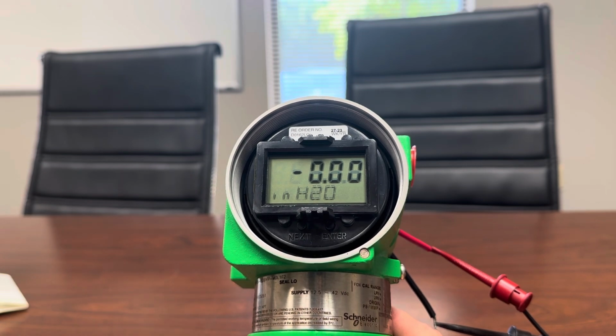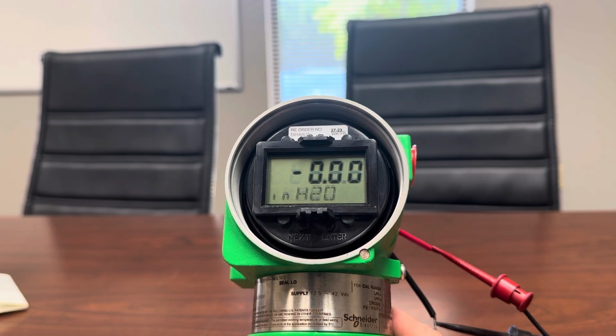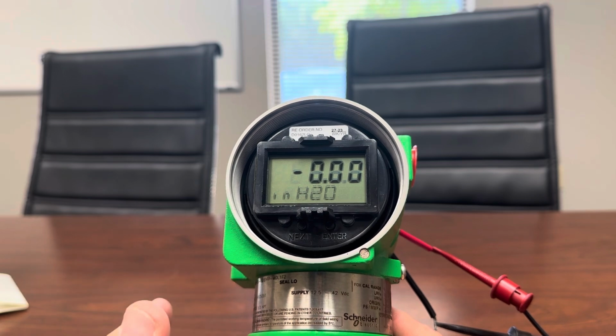So let's say, for example, you're measuring level in a tank and you have a calculated URV of 124.5 inches of water column, or inches of H2O, 124.5. Of course, you've done your calculation where you've taken your linear distance in inches from the midpoint of the process connection at the bottom of the tank, or your 0 point, measured in distance to your 100% or your 20 milliamp point, multiplied that by the specific gravity, and came up with 124.5 inches.